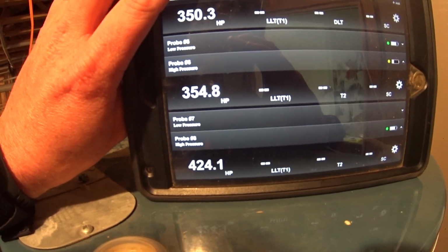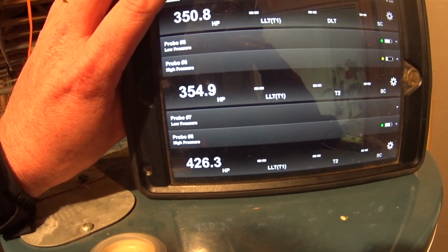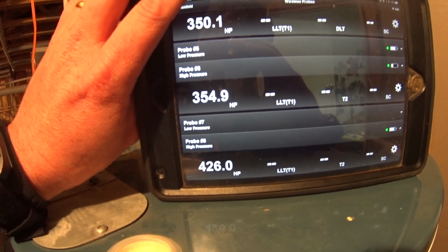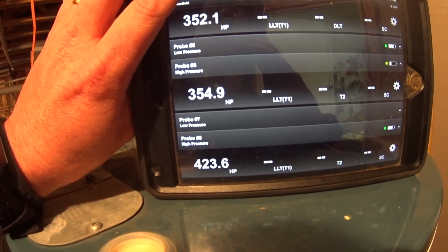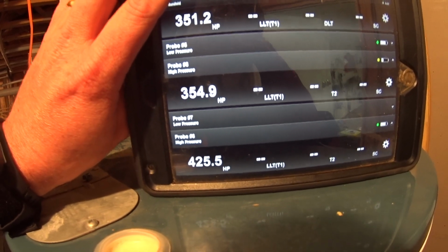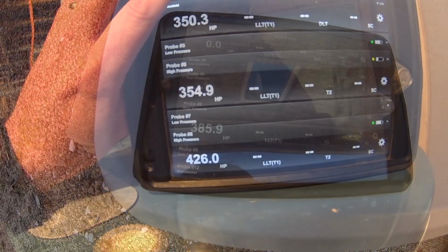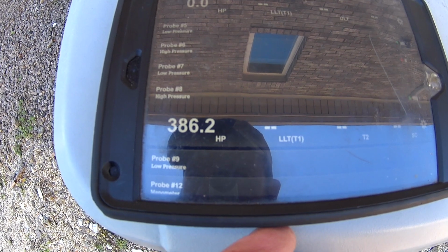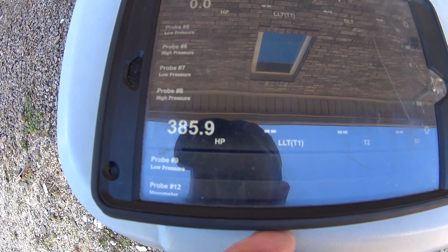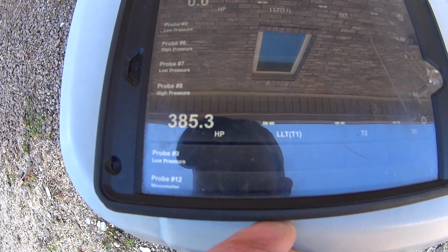But from here, what I'm going to do is isolate that one circuit, or leave it isolated on the refrigerant piping, and then separate the electrical so that I can operate the system with the 4 air handlers that are not leaking. So the circuit that had the 425 psi pressure test has dropped to 385 over the last, I'd say, 30 minutes or so. The rest of the circuit did not drop, but I'm in the process of evacuating the other circuits.